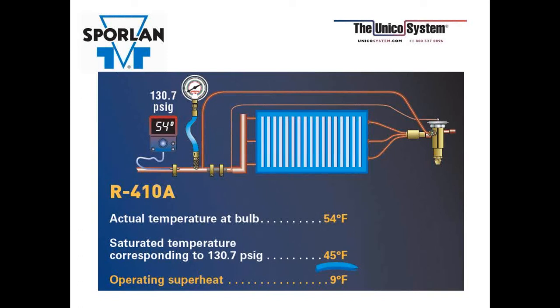The lowest amount of superheat you can have is 0. You cannot have a negative superheat, so if you come up with a negative number, you've done your math wrong. 0 degrees superheat means you have 100% liquid at the bulb or beyond, and if you have at least 1 degree superheat, it means you're not in a flooded condition.